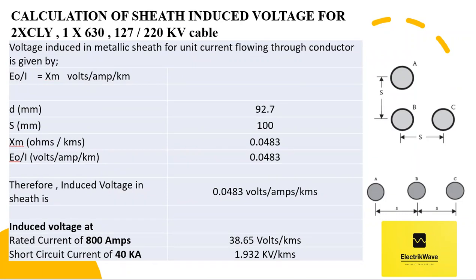As explained in the previous slide, the calculated induced voltage in the sheath based on the considered input is 0.0483 volts per ampere per kilometer. So the induced voltage for the rated current of 800 amperes would be 38.65 volts per kilometer, and at short-circuit current the induced voltage shall be 1.9 kV per kilometer. This will help to decide cable sheath voltage limiting requirements and size of conductor.